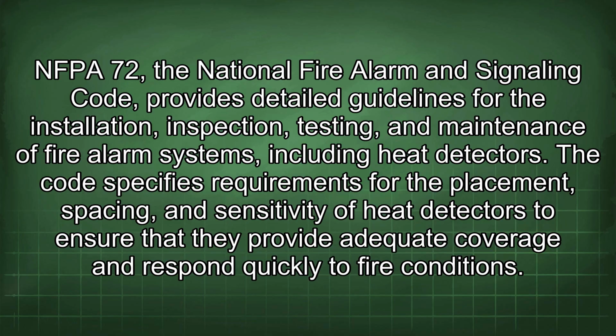NFPA 72, the National Fire Alarm and Signaling Code, provides detailed guidelines for the installation, inspection, testing, and maintenance of fire alarm systems, including heat detectors. The code specifies requirements for the placement, spacing, and sensitivity of heat detectors to ensure that they provide adequate coverage and respond quickly to fire conditions.